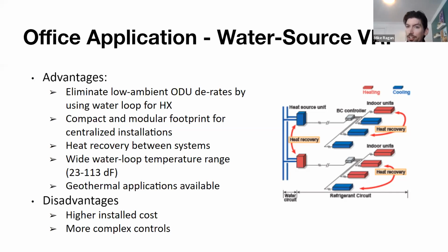With water source VRF, what's interesting is you could actually further recover heat between systems. Now, with air source, everything is just within a refrigerant network. You can transfer from one location to another in our refrigerant network. Because there's a common water heat sink here, you're actually going to be able to recover it from one source to another. So if you have one floor that's constantly in cooling mode, it's just pulling all that heat out of that space, you could send it up to the floor above where everyone's in heating mode and needs it. So that's an additional efficiency gain that you would get from water source VRF equipment.